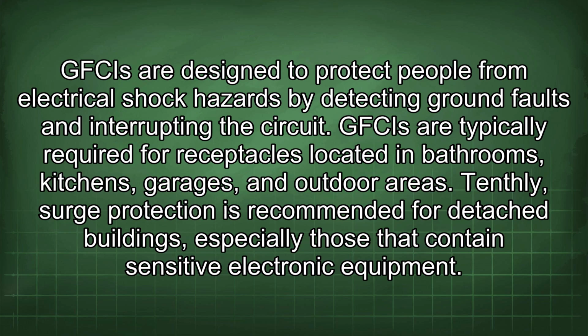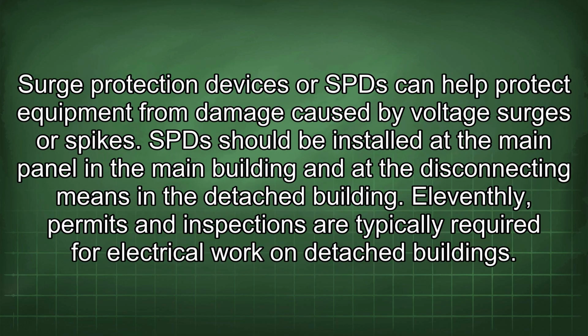Tenthly, surge protection is recommended for detached buildings, especially those that contain sensitive electronic equipment. Surge protection devices or SPD can help protect equipment from damage caused by voltage surges or spikes. SPD should be installed at the main panel in the main building and at the disconnecting means in the detached building.